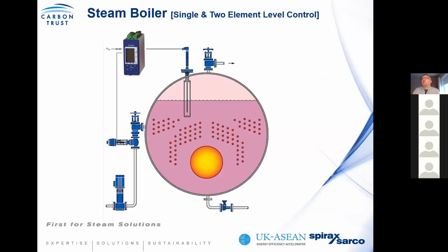So what you should be doing is, as part of your single element control, which is basically looking at the level in the boiler and controlling a valve, you would then add a steam meter on the output. This creates two element control. And what the second element does is that, through a cascade control, it looks at the level whilst also monitoring the steam consumption. So in other words, it would add water at a proportional rate to the steam being generated, as measured by the steam meter, within the control parameters of the level probe.